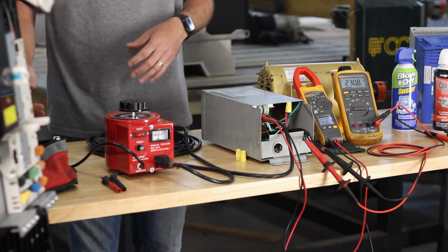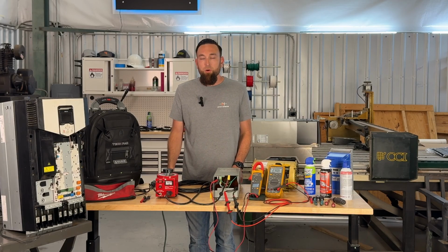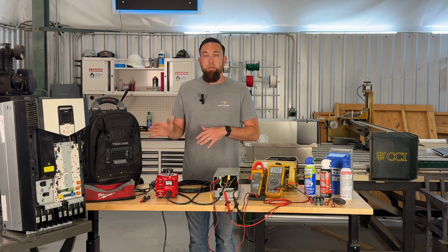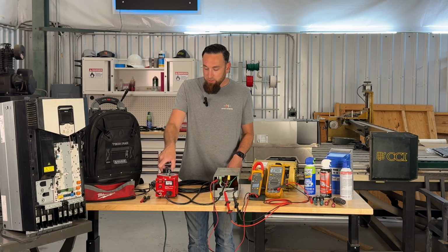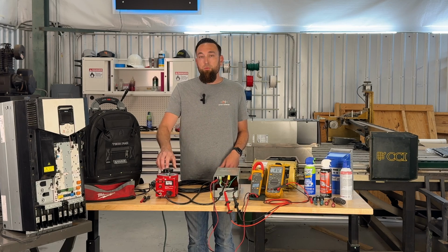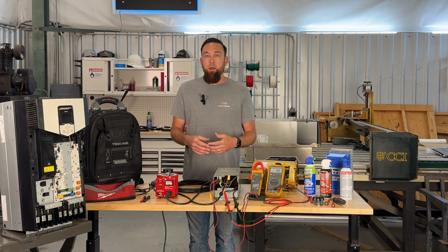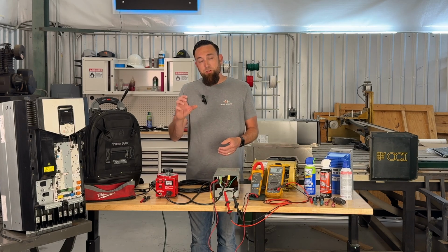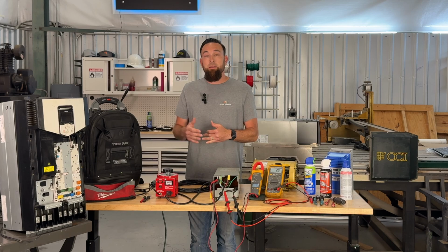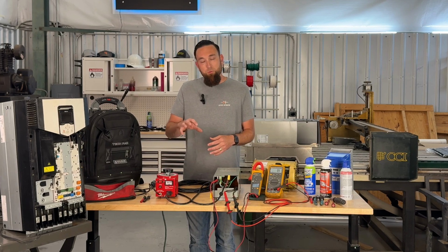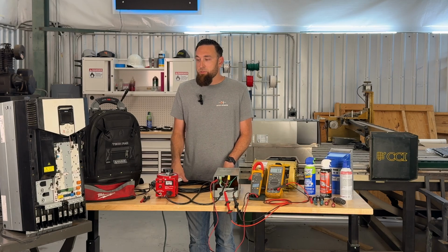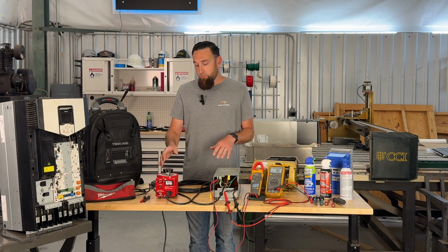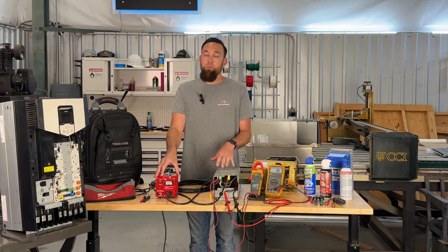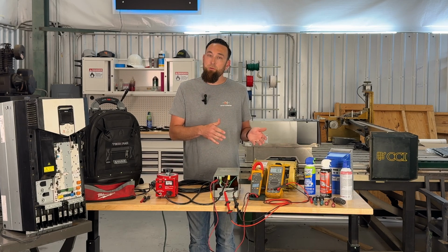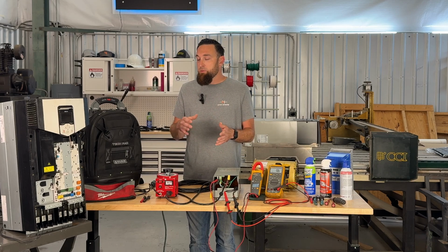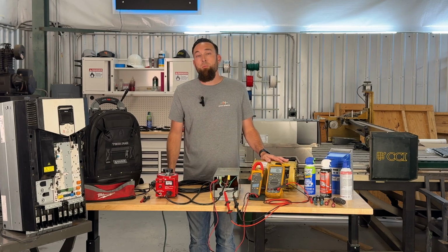So that's how we take normal extension cord power, just 110, and boost it up for this application. This is a very low current application, so we don't need huge availability of power - we're just slowly raising the voltage and letting it sit there. It's not going to be draining a lot. We're slowly charging the capacitors, so we won't be able to run a motor with this setup, but we will be able to reform the capacitors. Once they get to full level, we can switch over to normal 3-phase power and start testing our motor.